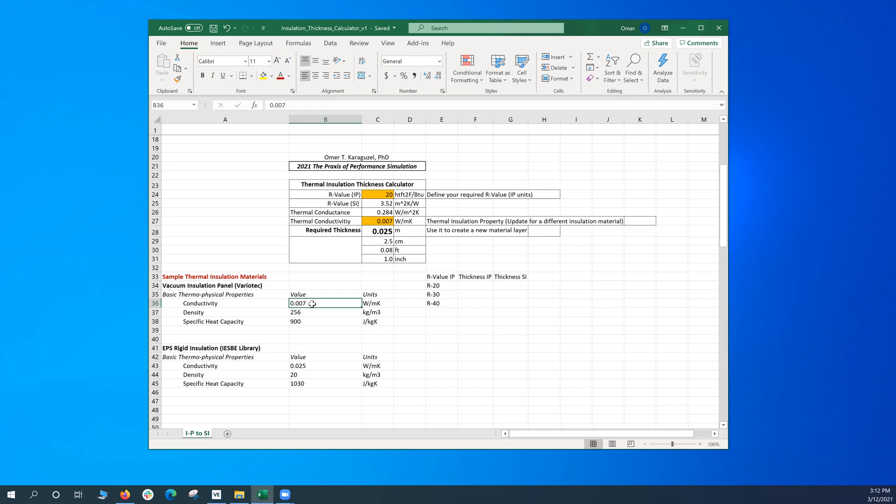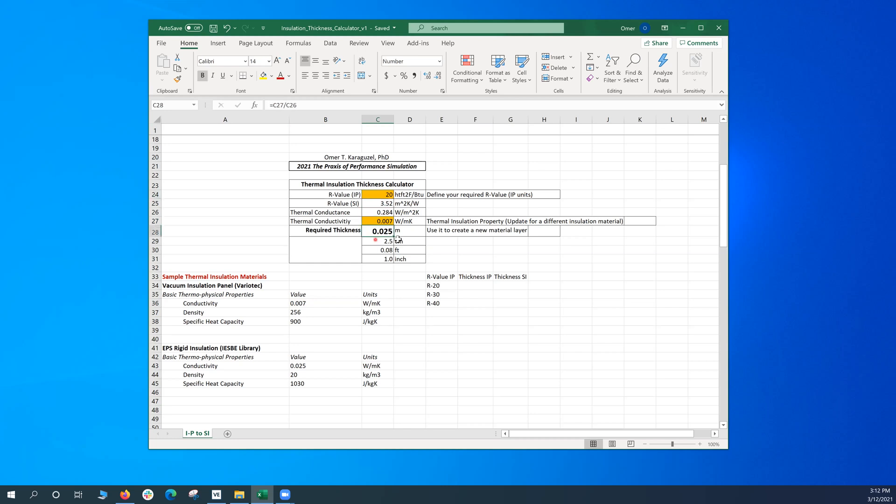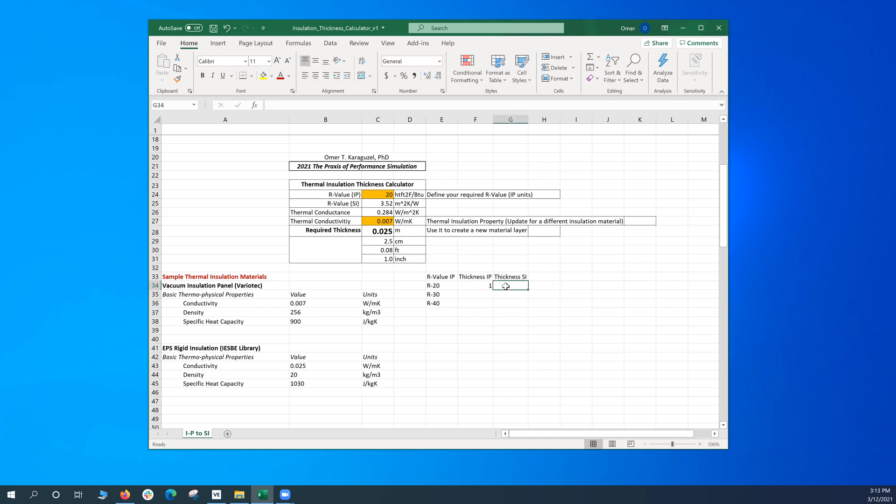So when I plug in the number, and this is my target R-value, I get 0.025 meters or 2.5 centimeters or one inch. So that's what I get from the tool. As a thickness, I get one inch in IP system and 2.5 centimeters in SI system.